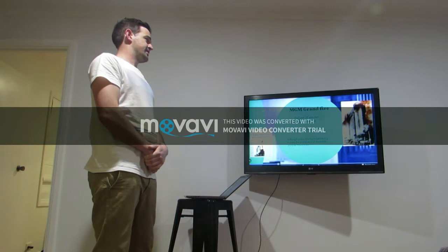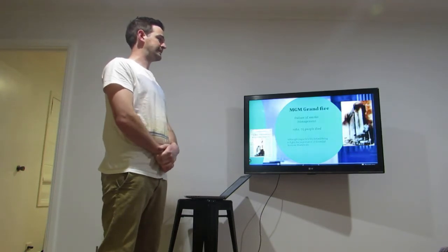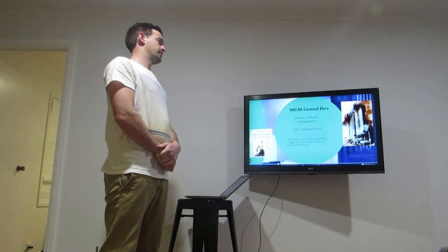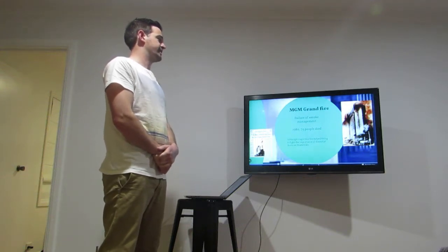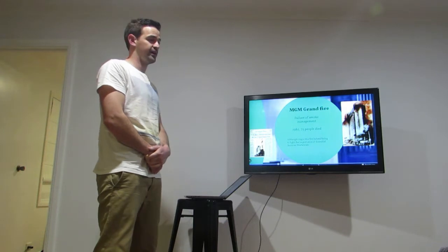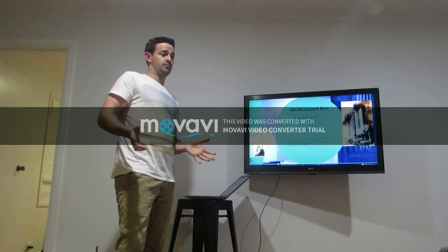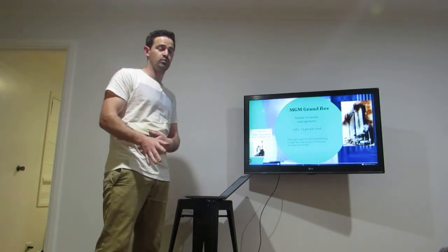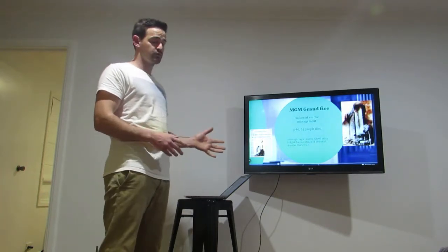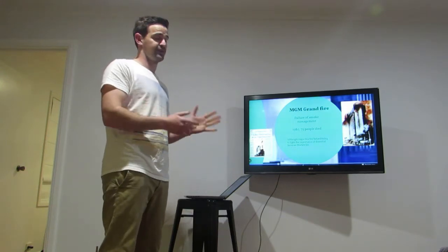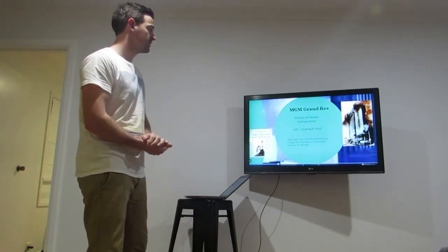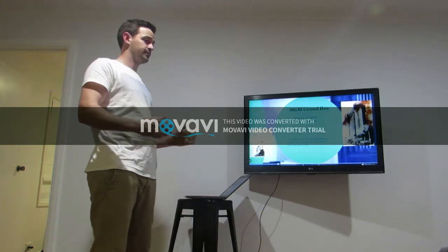The MGM Grand fire in the States in 1980 was a big issue with smoke management and the failure of fire dampers. 75 people died. Now this fire was generated on the ground floor in a cafe, and the smoke actually travelled the whole way through the building. Some floors were perfectly fine, while on others people weren't saved. Some apartment rooms next door to another were perfectly fine, and the very next one was completely filled with smoke. Although this was tragic, it has helped bring to light the importance of HVAC essential services worldwide.